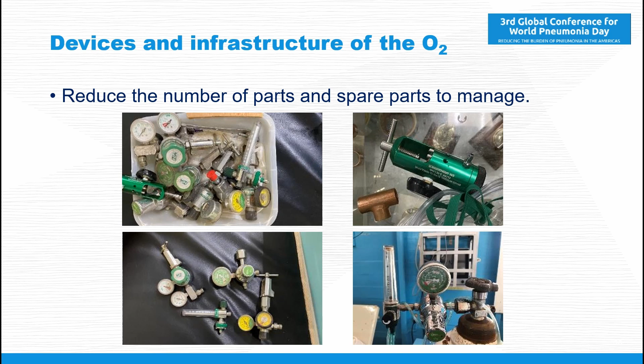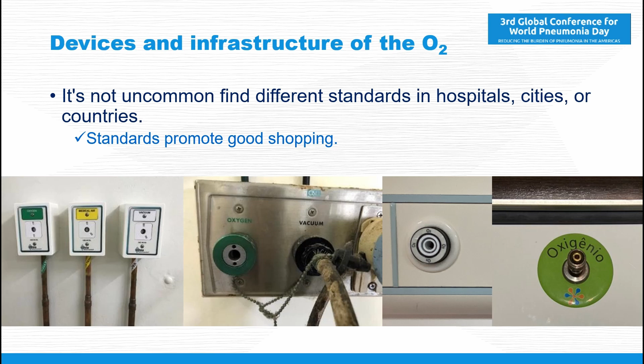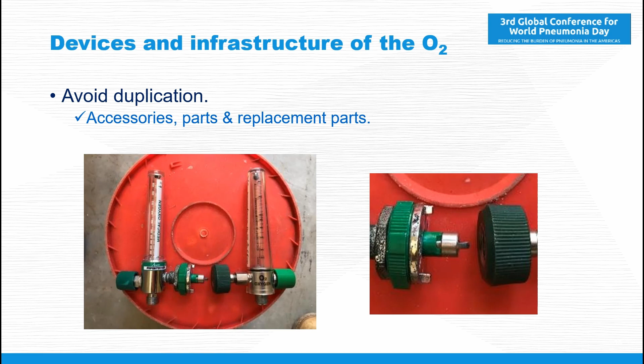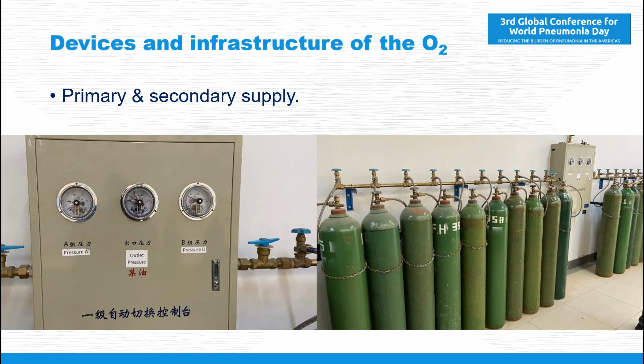The same thing may occur in oxygen outlets. If it's not standardized, the same problem of duplication will appear in the hospital and will increase the tasks that engineering must do to manage these devices. This is an example of two flow meters that do the same thing but with two different types of connection. The lack of specialists may lead to the substitution of a system like this, which permits managing not only primary and secondary supply but also regulating the pipeline pressure, by systems like this. That's more unsafe because there is only one pressure regulating station.